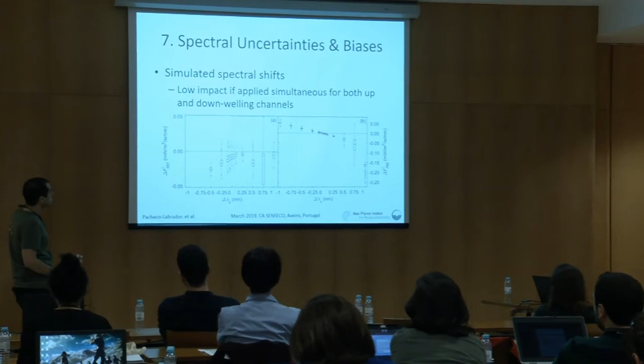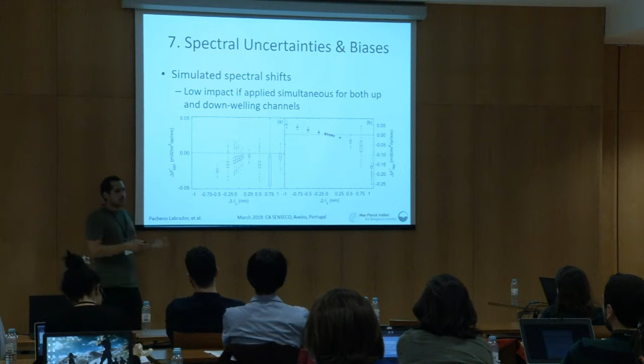So we came up with this model where from the data she was characterizing how the center of the band and the full width at half maximum, the width of the band, was changing according to temperature for each band, and we again went to the simulation. So we propagated all this with uncertainties and came up with these results. So again, it's not the same result if the shift occurs to both channels or if the shift is occurring separately in each of the channels. So if for any reason you have only one of the channels maybe expanding more than the other or changing more than the other, so there is a relative shift, then maybe the fluorescence actually is compromised.